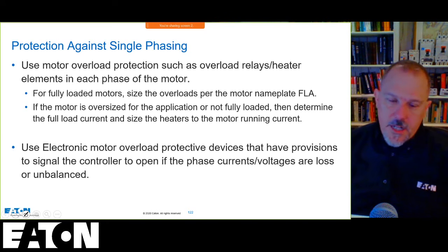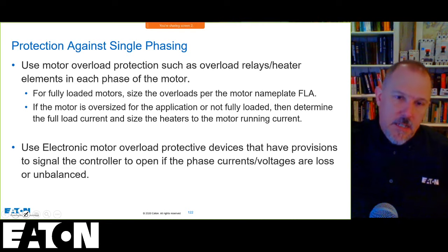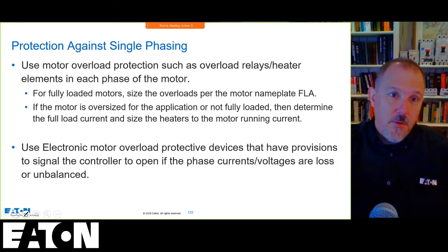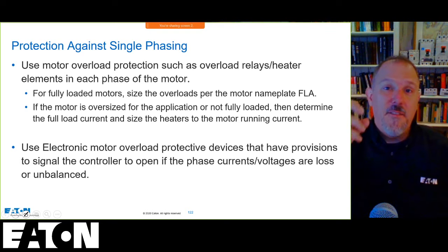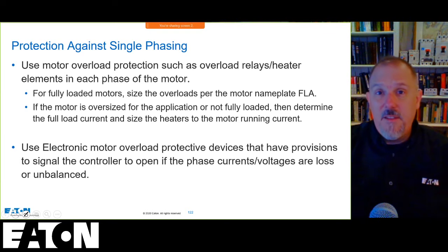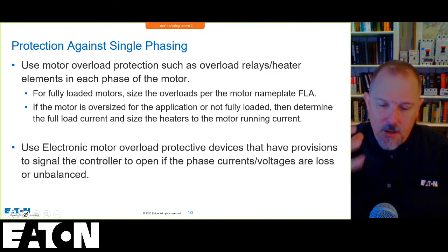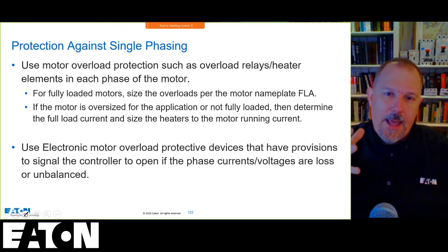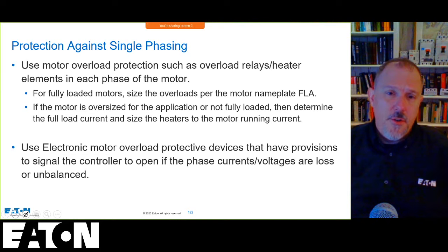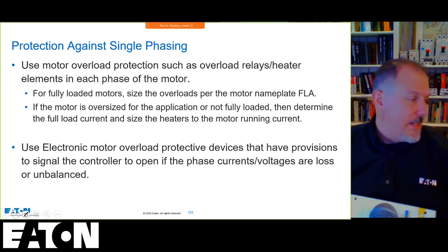Electronic motor overload protection. Again, the more expensive the motor, the more protection I'm going to be providing on that motor. I'm going to pick up negative sequence. If I have a very expensive motor, I can have negative sequence relays and RTDs in there. All of those things add up. For your smaller motors, you're relying on your overload heater elements, et cetera.